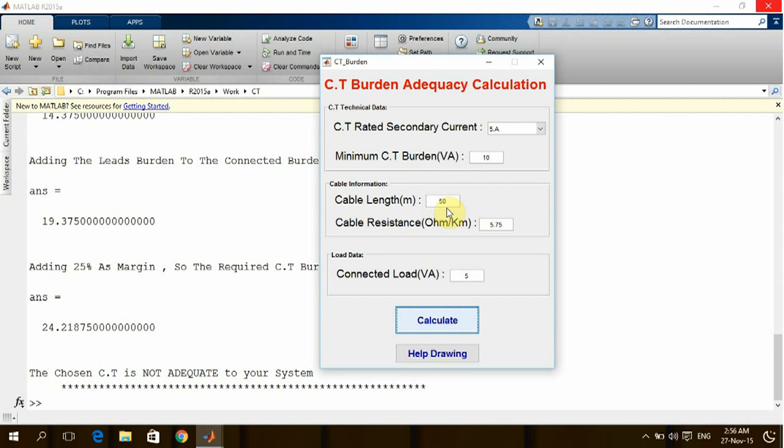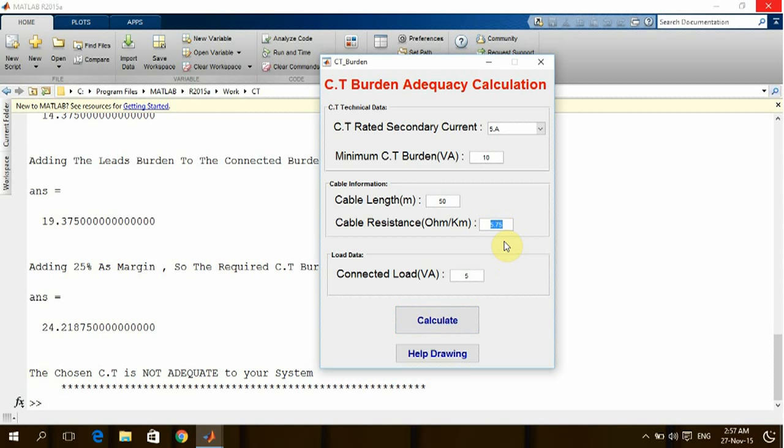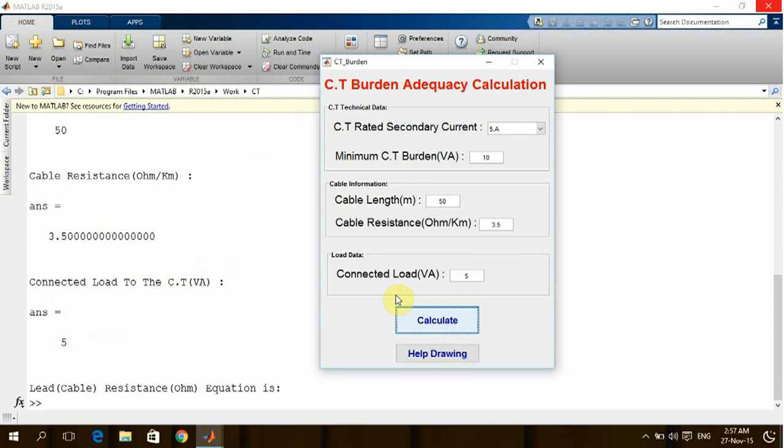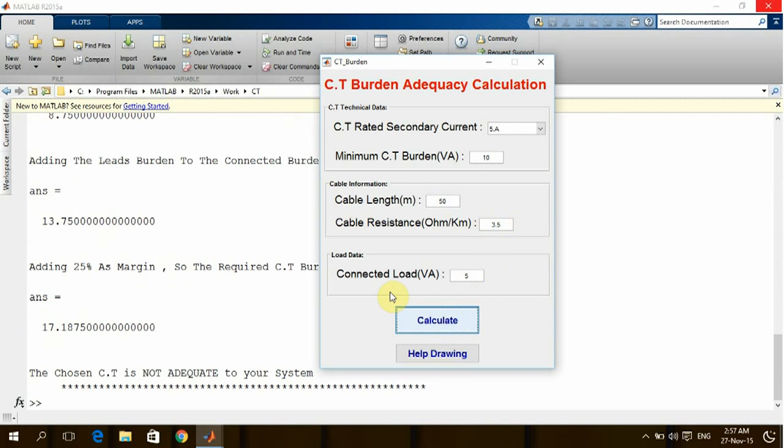The cable length is also something fixed based on the layout of the project. So the design engineer maybe can decide to increase the cross-section of the cable. Rather than using four square millimeter cable, he is going to use six, so the resistance will be decreased since the cross-section will be increased. Rather than five, let's consider by increasing the cross-section it will be 3.5 ohm per kilometer. Again we are going to check—still the CT is not adequate.